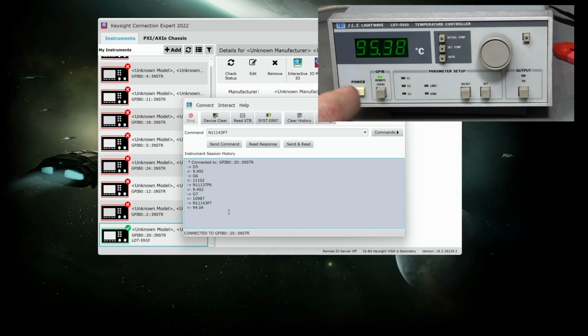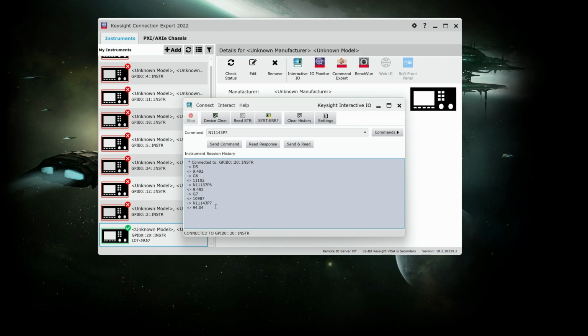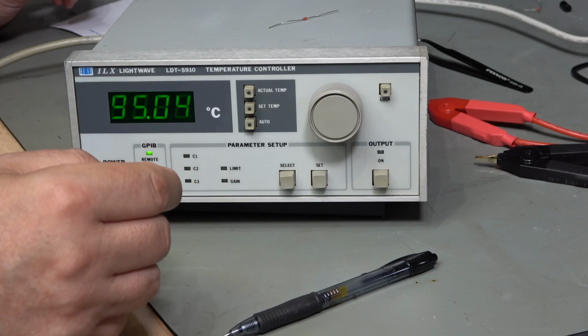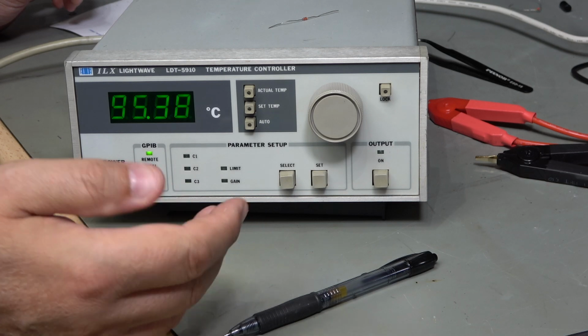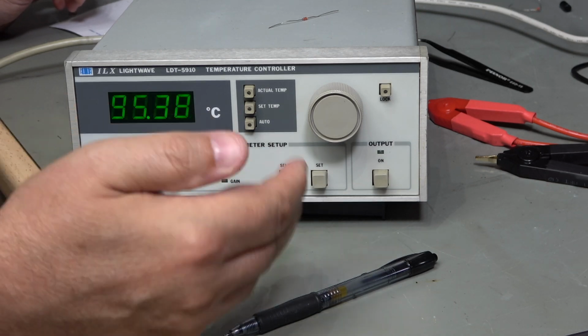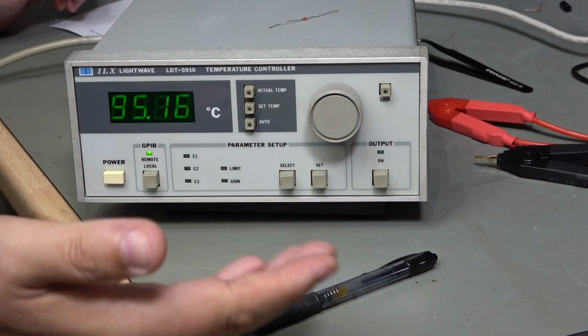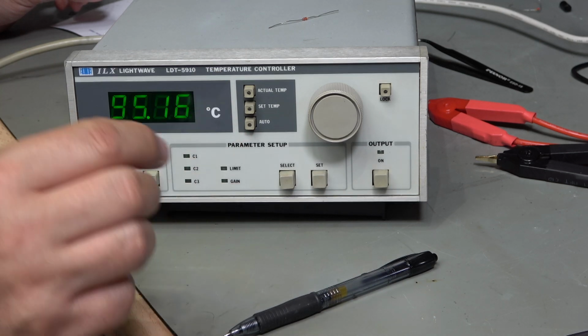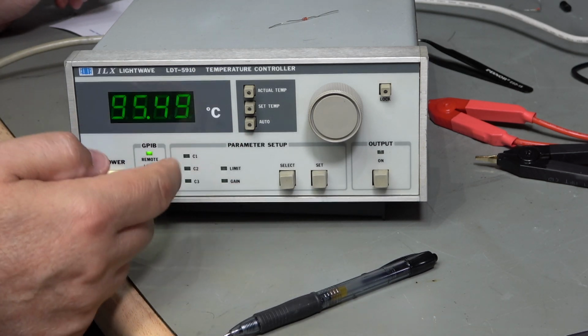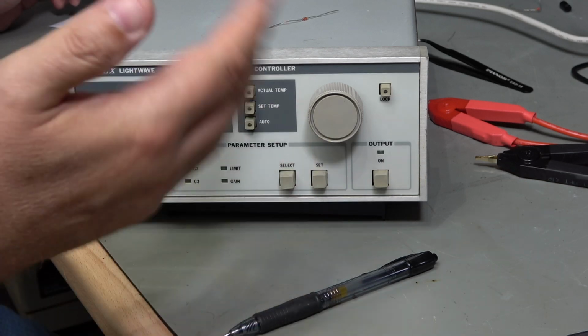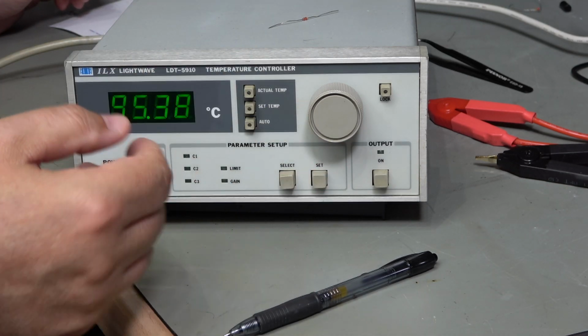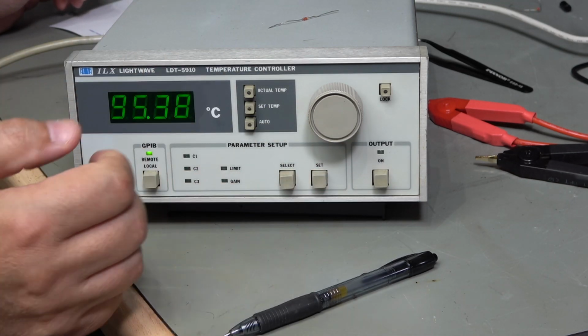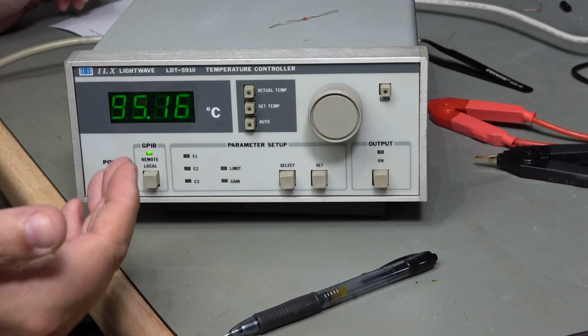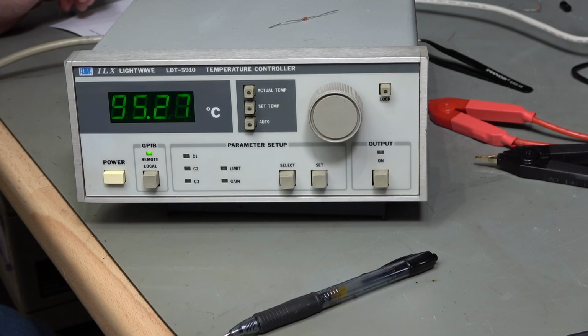Okay, so that's that bit done. Now we can continue, we can connect up an amp meter to the outputs, and we can do a similar calibration, essentially exactly the same method for the current limit setting on here. So essentially we set an amp, we see how close to an amp we're outputting, and then we just adjust a factor to make it work better. So we're just trimming a DAC is all we're doing for that. So it's the same principle.